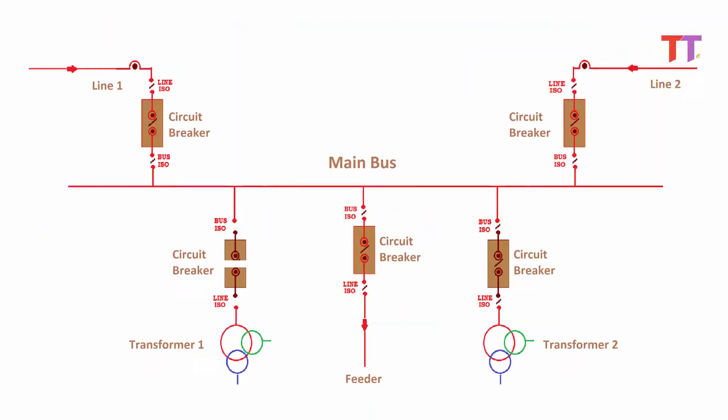Disadvantages: maintenance activity of any bay or equipment such as a transformer is not possible without service interruption of that particular bay or equipment. Also, in case of a fault on the bus or bus maintenance, all the bays connected to the bus get interrupted.